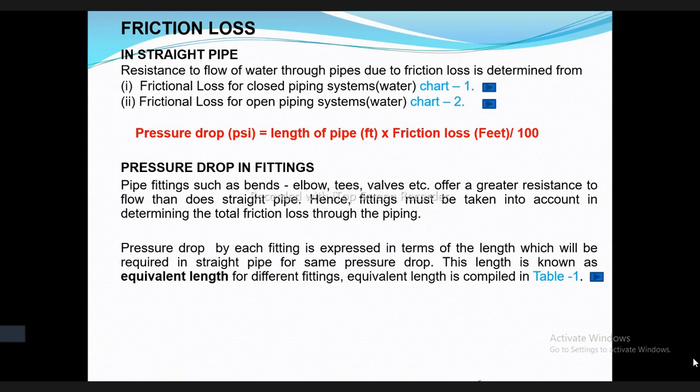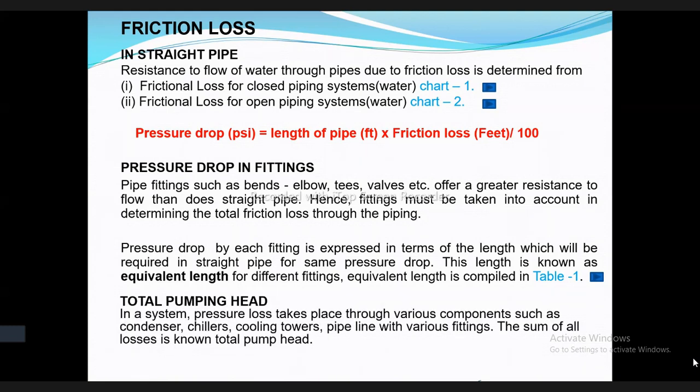Total length. So if your manufacturer gives you a pressure drop across a valve in maybe kgs or in any other units, then you have to convert that into equivalent length, or you have to add that separately. Whatever pipe length you have, plus the equivalent length of whatever is the pressure drop across that valve. I hope it is clear.